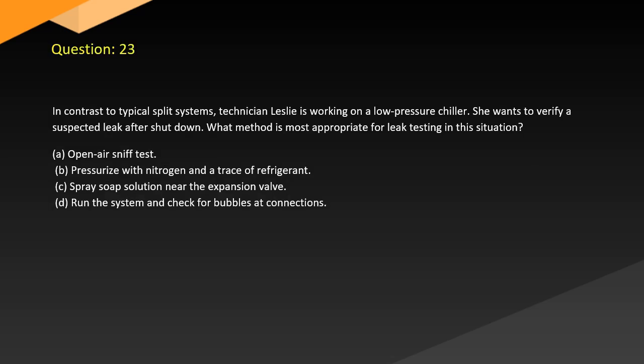Question 23. In contrast to typical split systems, technician Leslie is working on a low-pressure chiller. She wants to verify a suspected leak after shutdown. What method is most appropriate for leak testing in this situation? A. Open air sniff test. B. Pressurize with nitrogen and a trace of refrigerant. C. Spray soap solution near the expansion valve. D. Run the system and check for bubbles at connections.